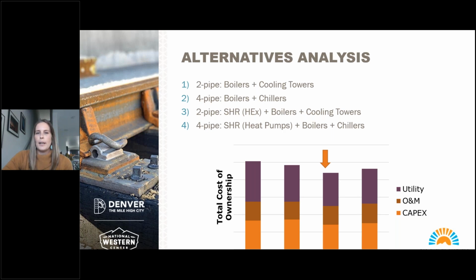They also evaluated whether a 2-pipe or 4-pipe configuration would be most appropriate. In a 2-pipe system, the plant sends a condenser water loop to the buildings, and the building HVAC system converts that to hot water and chilled water loops at the building. In a 4-pipe system, that heating and cooling conversion happens at the plant, and the plant sends out a hot water and chilled water loop straight to the buildings.